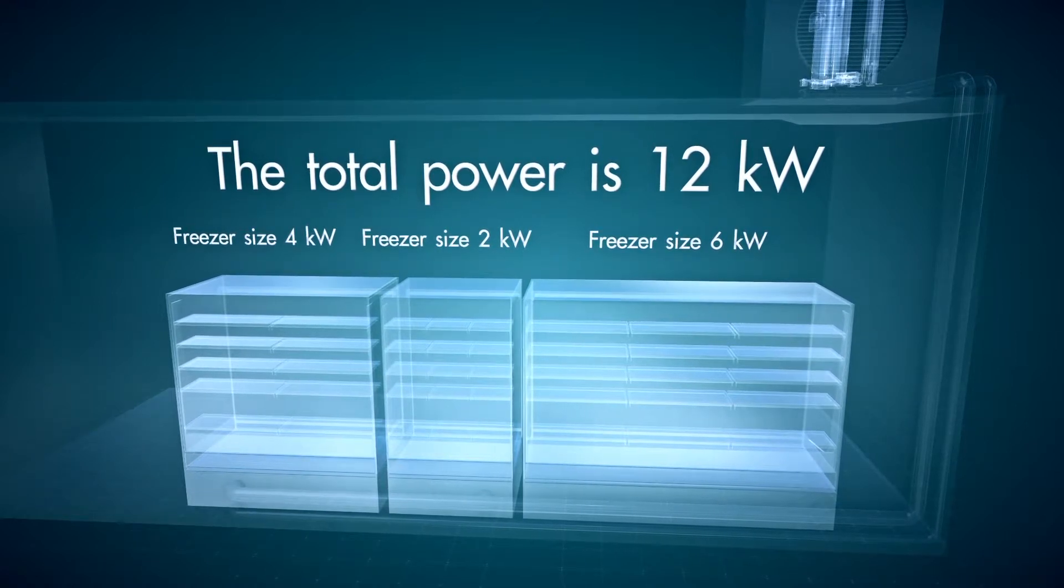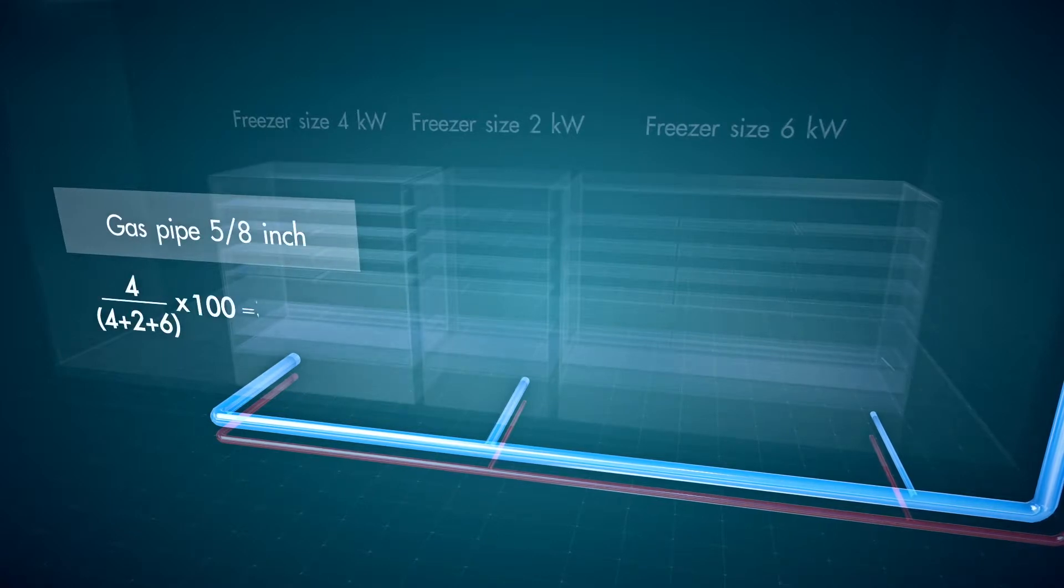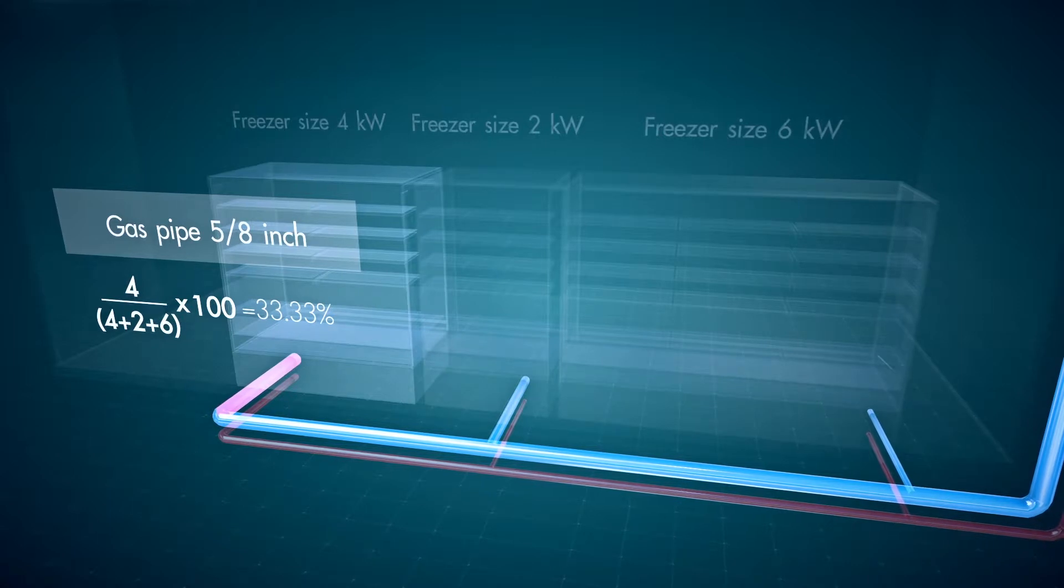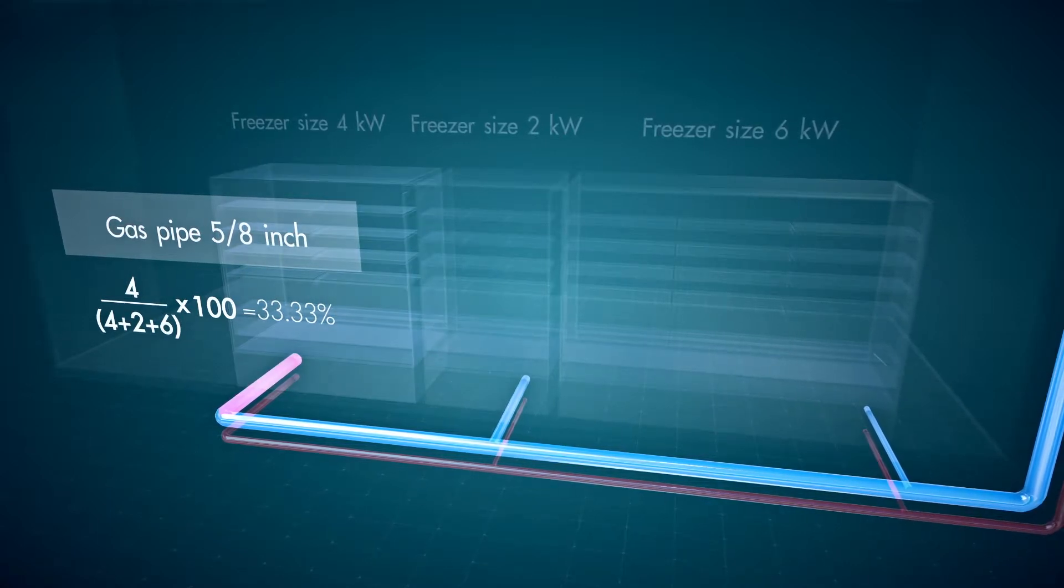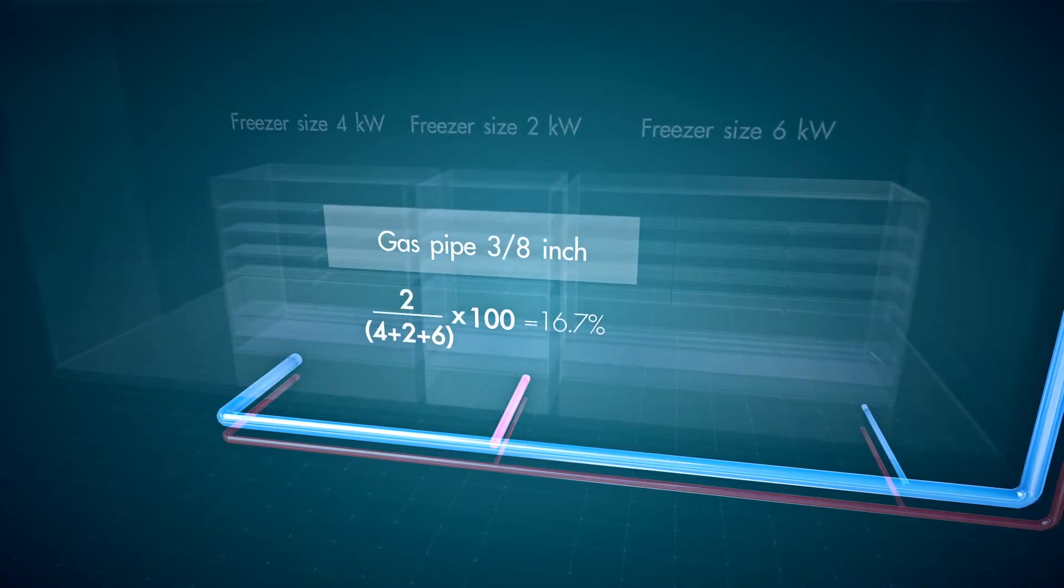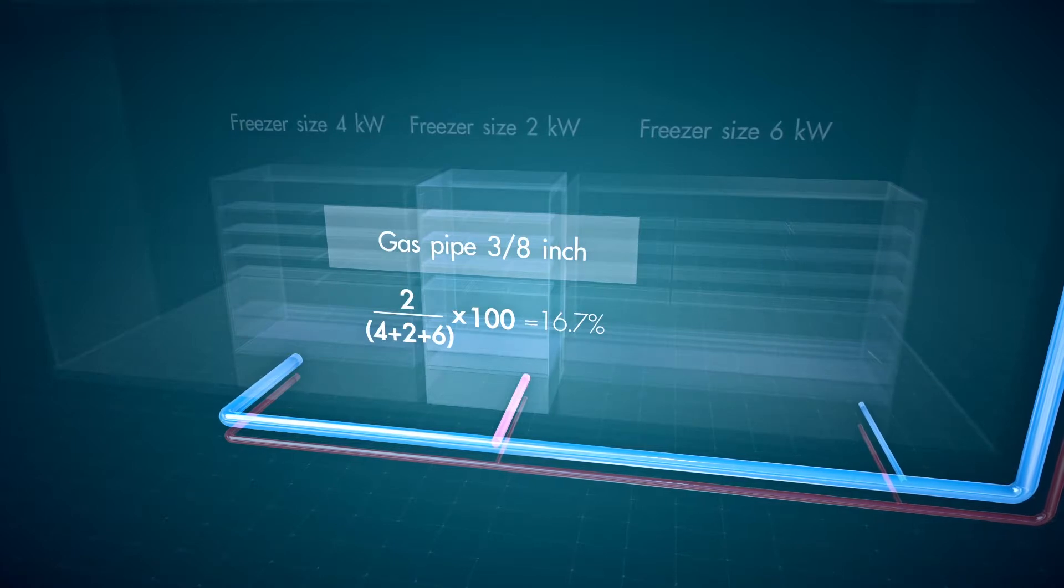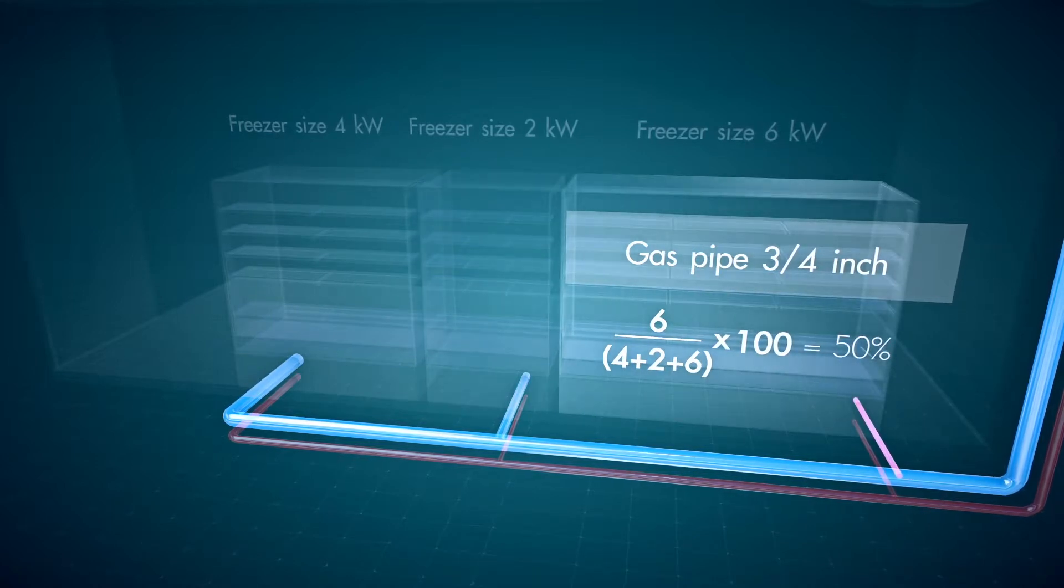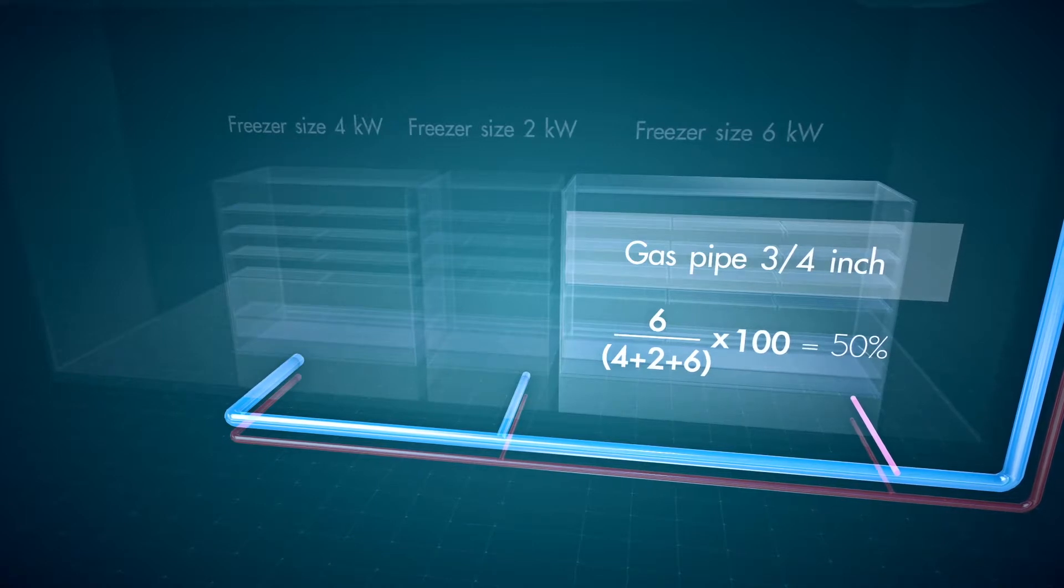The size of the pipe connecting to the 4 kW refrigerating unit would be ⅝ inches in diameter with the flow rate equal to 33%. The size of the pipe connecting to the 2 kW refrigerating unit would be ⅜ inches in diameter with the flow rate equal to 17%. The size of the pipe connecting to the 6 kW refrigerating unit would be ¾ inches in diameter with the flow rate equal to 50%.